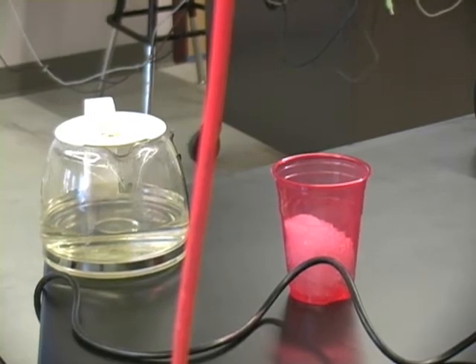A long way of repeating the same thing because I can't say it enough. When you take images with the thermal imager, you have to know the properties of what you're looking at. So if you're trying to measure the performance of glass on a building, you have to know it's going to reflect whatever's on the side of it. It's not going to see what's on the other side of it.